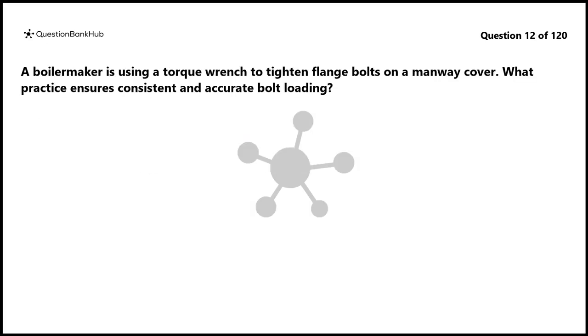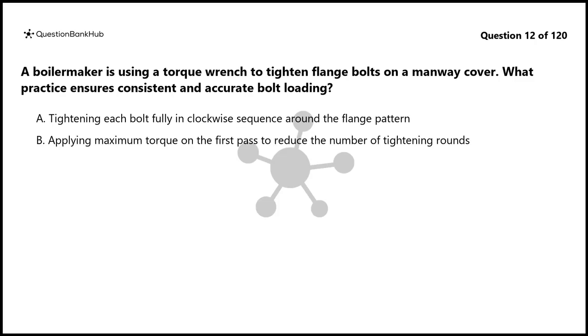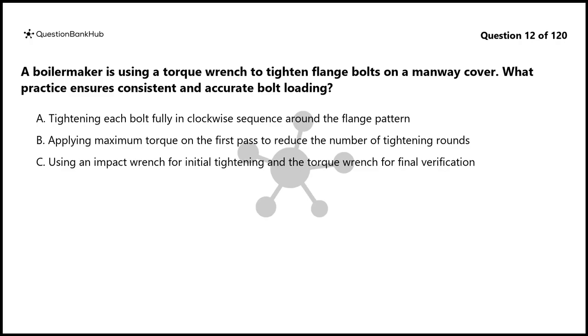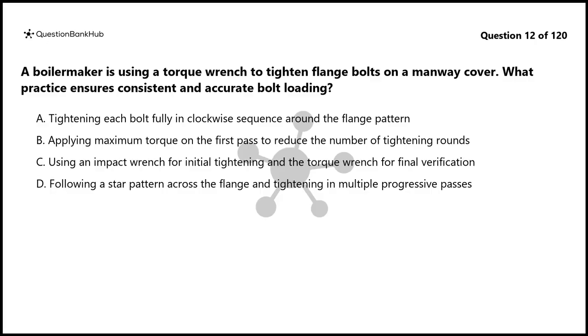Question 12. A boilermaker is using a torque wrench to tighten flange bolts on a manway cover. What practice ensures consistent and accurate bolt loading? A. Tightening each bolt fully in clockwise sequence around the flange pattern. B. Applying maximum torque on the first pass to reduce the number of tightening rounds. C. Using an impact wrench for initial tightening and the torque wrench for final verification. D. Following a star pattern across the flange and tightening in multiple progressive passes.